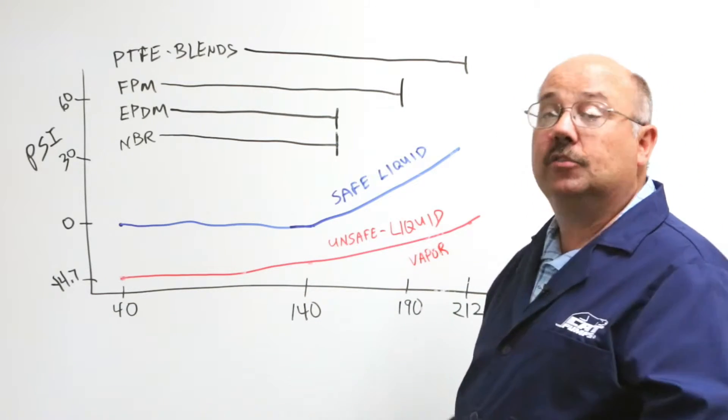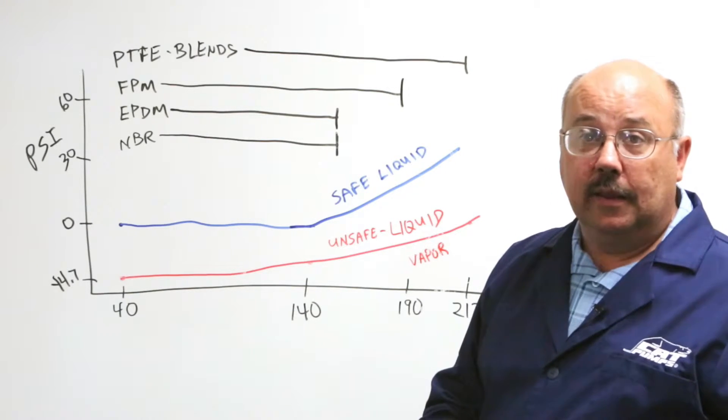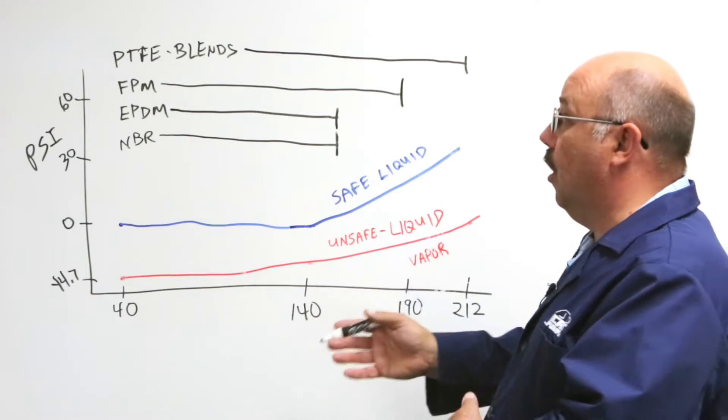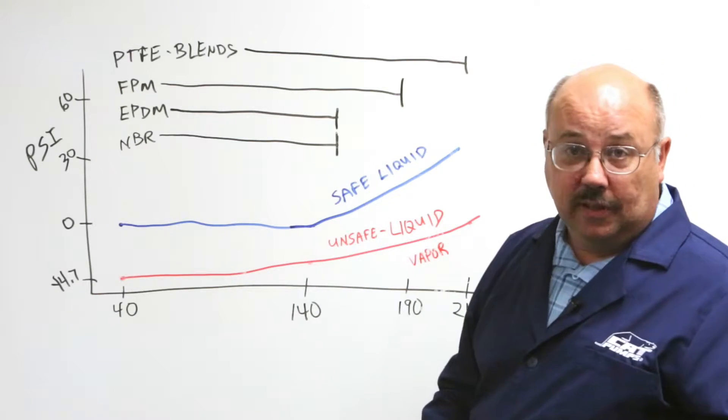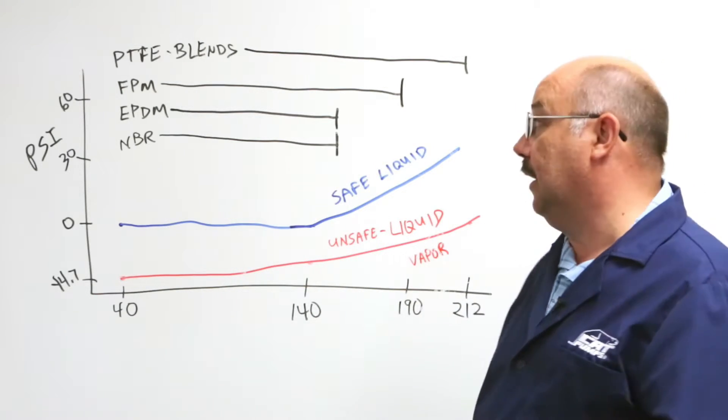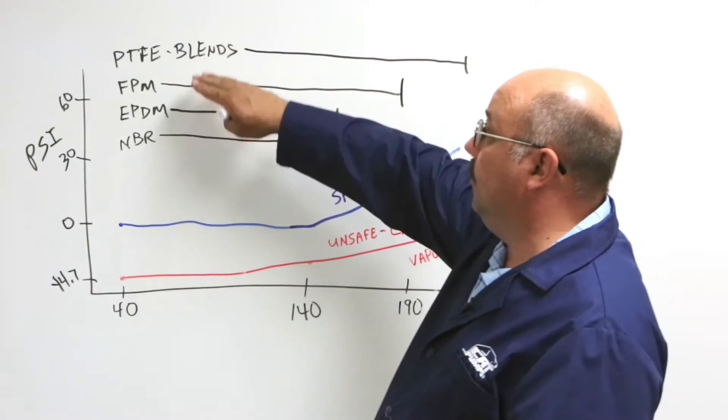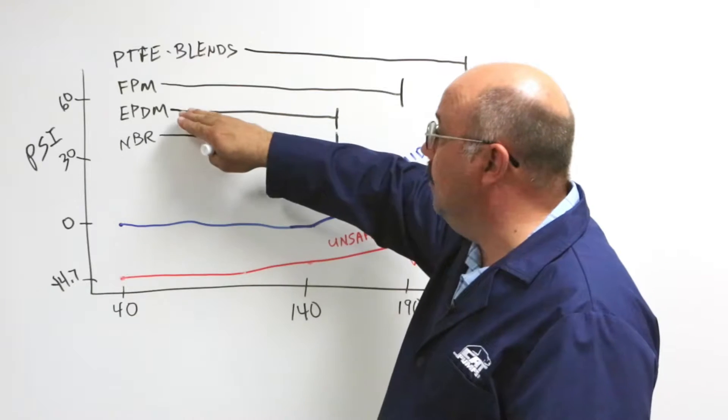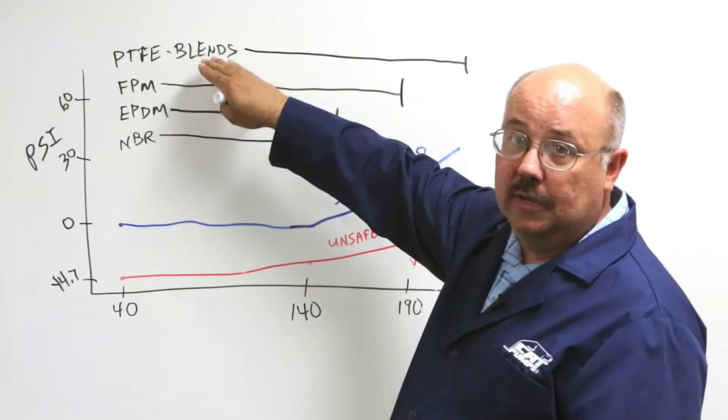And so depending on your temperature will kind of depend on which elastomer you pick. Now the elastomer also has to meet the chemical compatibility of the liquid. All of these will pump water. They're all compatible with water. But then you get into other types of liquids and chemicals in them and things like that where you have to evaluate. Is FPM the right material or EPDM or NBR or do we need the PTFE?